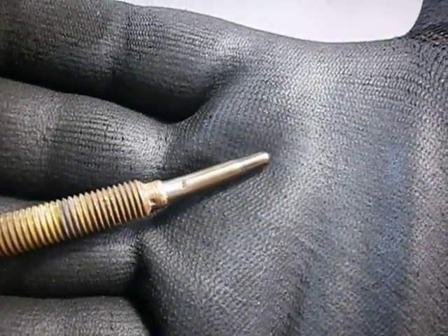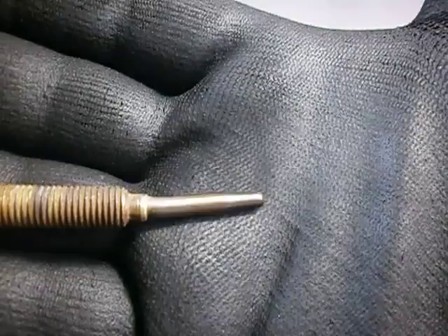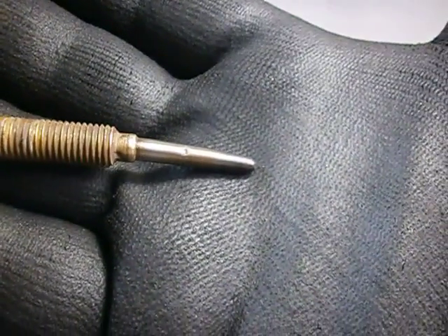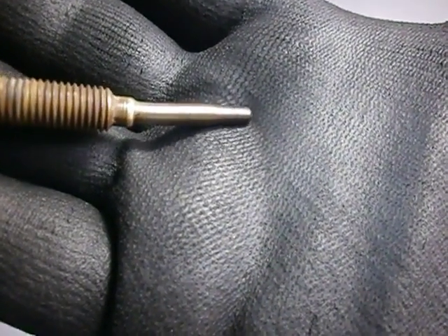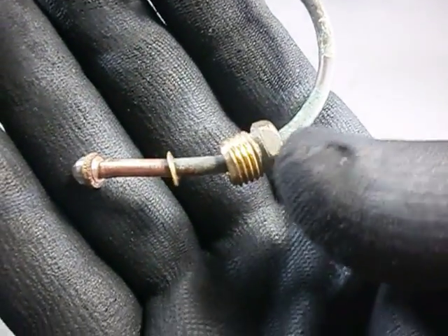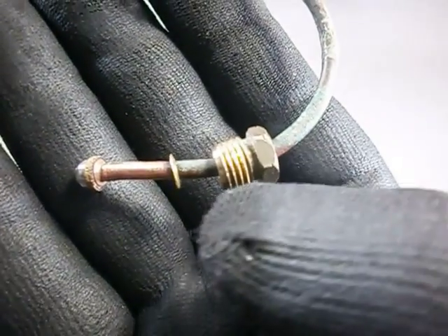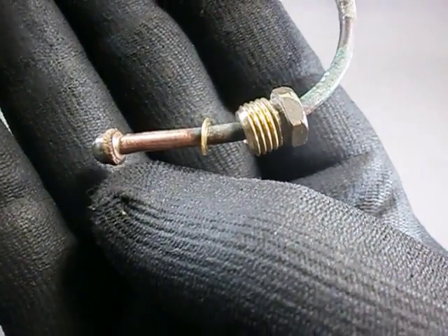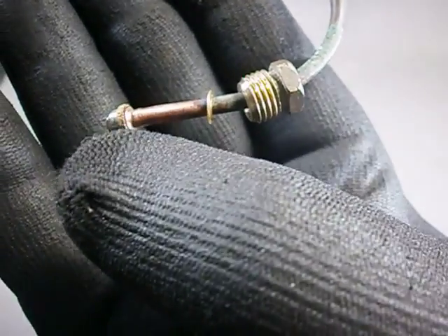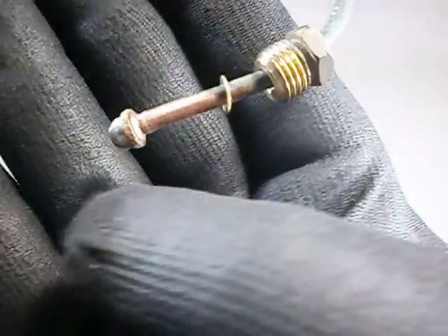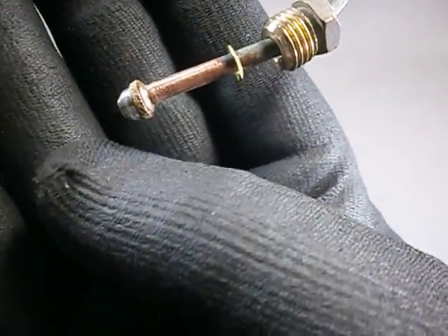So here we have the hot junction free from the accumulated oxidation. The tip is encased in stainless steel or something. The connector is also clean. Although it must have its raison d'être, I am not particularly impressed with this kind of connection, because we have at least four or five points of contact in series which can become points of failure. The tip of the connector is apparently made of stainless steel.